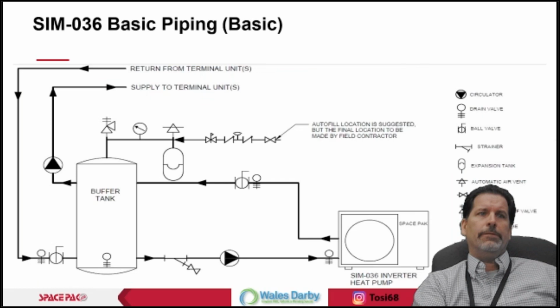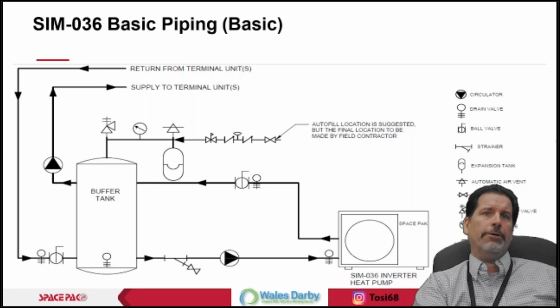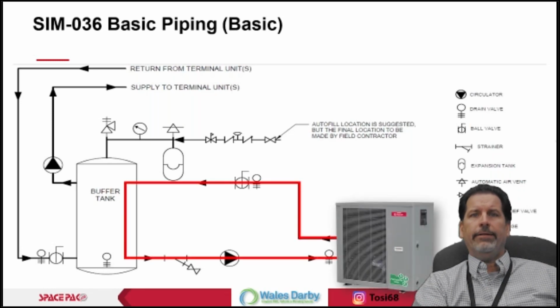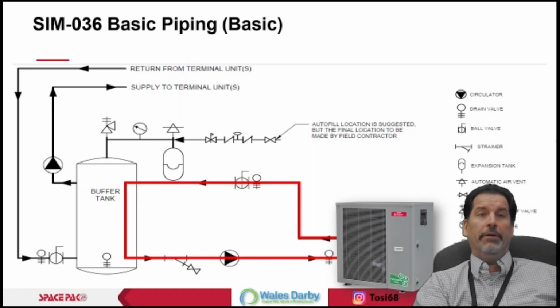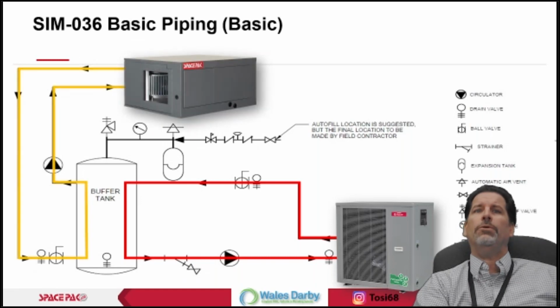All right. A lot of this should look very similar, pretty comfortable. What we do in the mechanical room, the only thing is, where's the boiler? Well, it's outside. It's outside in the yard, right? We have this buffer tank. The only thing that heat pump is concerned about is maintaining that tank's temperature. That becomes the battery. That almost becomes the source for what we do inside. As long as that outdoor unit is pumping BTUs, regardless of the water temperature, we're going to satisfy that tank. And as we get a call, all things come to life and we deliver comfort.